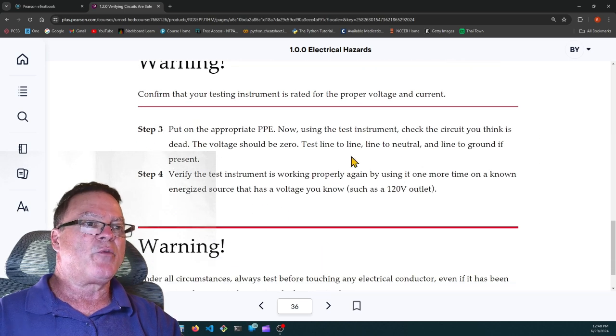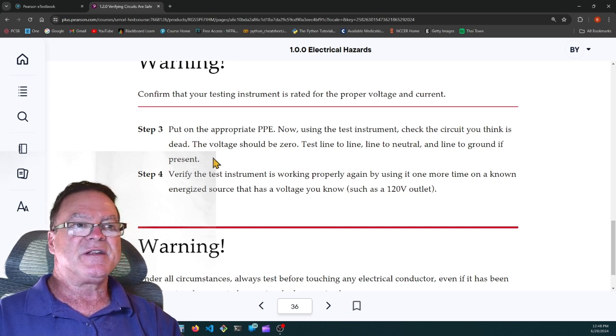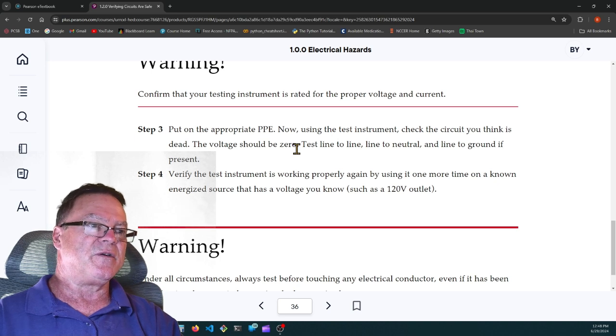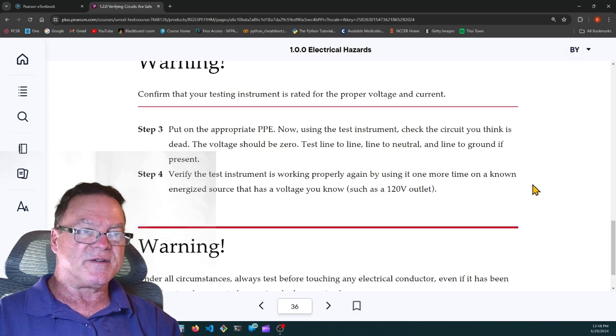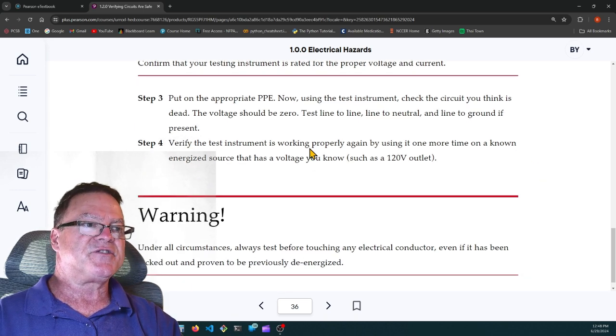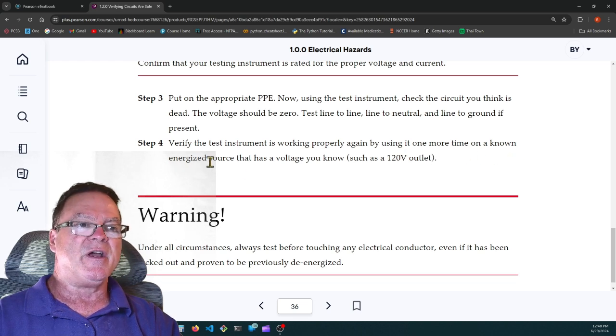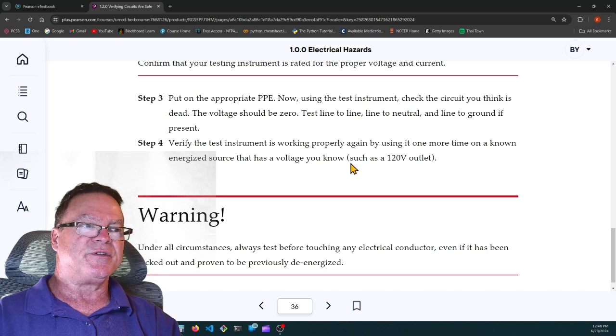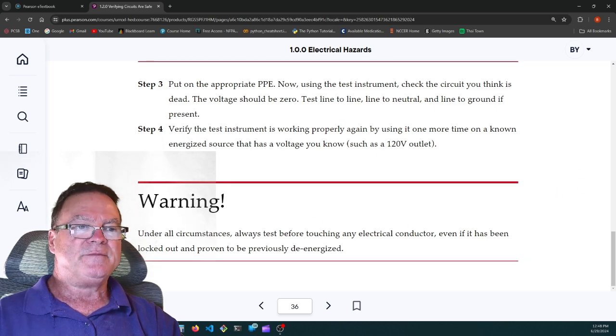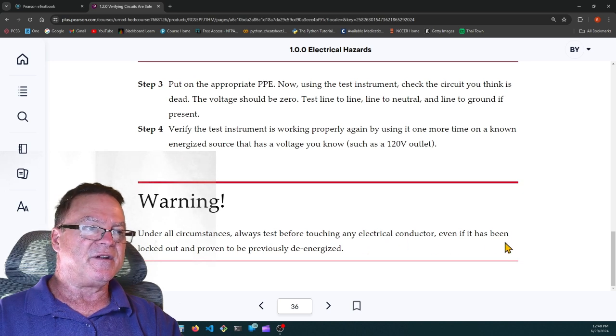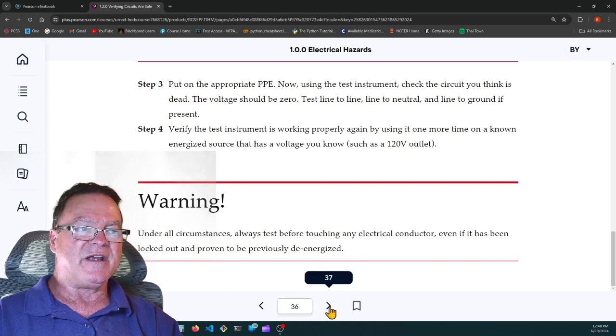Step 3, put on the appropriate personal protective equipment. Now using the test instrument, check the circuit you think is dead. The voltage should be 0. Test line to line, line to neutral, and line to ground if present. Step 4, verify the test instrument is still working properly by using it one more time on a known energized source that has a voltage you know. Warning: under all circumstances, always test before touching any electrical conductor, even if it has been locked out and proven to be previously de-energized.